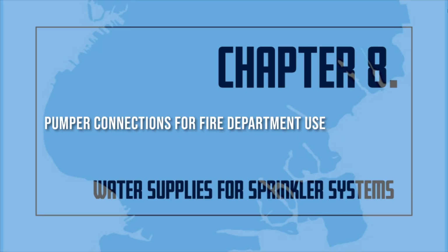Care should be taken that the standpipe and the sprinkler connections are properly marked because the connections look the same. The exact purpose of each fire department connection should be shown nearby or on the fire department connection itself. The New York City Building Code requires fire department connections to be color-coded. The fire department connection to an automatic sprinkler system shall be painted green. The fire department connection to non-automatic sprinkler system shall be painted silver. The fire department connection to a standpipe system shall be painted red.